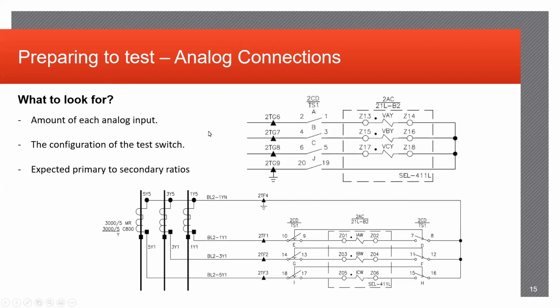So configuring the test switches, making sure that you correctly identify the phases per the inputs to the relay. So you want to identify and verify that phase A from the PT source is going into the phase A port on the relay. Same for B and C, and making sure you have your reference. Same here for your phase A, B, and C currents as well. You want to verify that they're coming off the correct CT. It's going through correctly polarity wise and got your return as well.